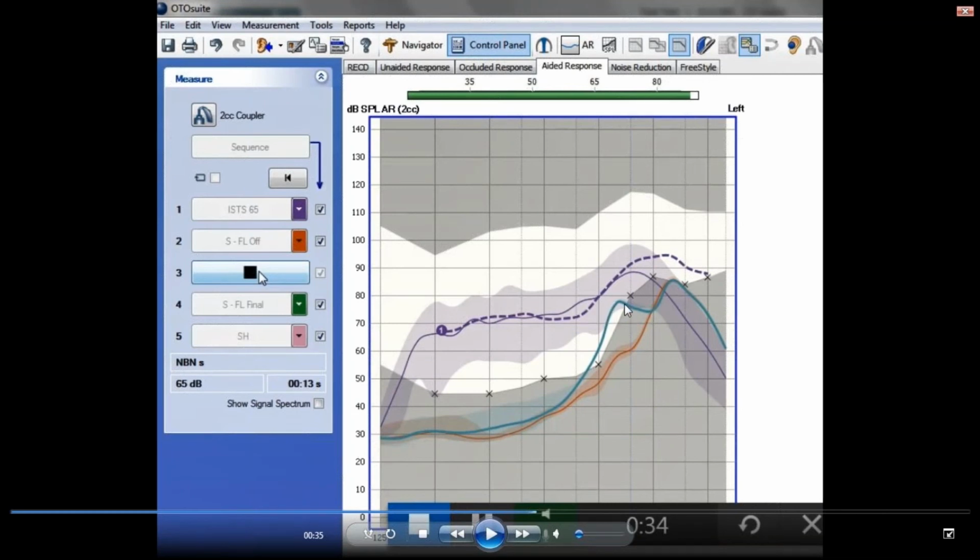So whenever you see two peaks, when you see the original peak and a lower peak, it's the lower peak that you want to fine tune. So when I look at this lower peak, because this is a transposition, it's moving it much lower. So I'm not just looking at the MAOF. I'm actually now down into the lower range of the MAOF. I can see that I do have audibility, but if I want to give a little bit of a stronger setting for stronger audibility, I have two choices.